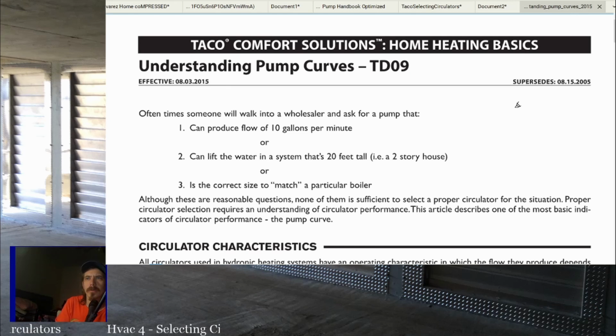Oftentimes, someone will walk into a wholesaler and ask for a pump that can produce 10 GPMs of water, or can lift water in a system's tank that's 20 feet tall or two-story house, right? Or is the correct size to match a particular boiler. Although they're reasonable questions, none of them are sufficient to select a proper circulator for the situation.